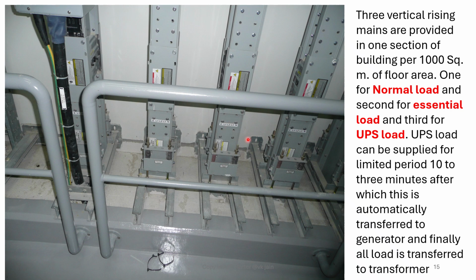Friends, the figure on left hand side shows the real life rising main systems, vertical rising mains, one, two, three. This real life vertical rising main system is provided for three different purposes. The first one may be normal, feeding the normal load only through the transformer. The second one may be feeding the essential load which comes through generators. And third one may be the load fed through UPS. So this rising main is connected to UPS and distributes the power to different items which are on UPS, mostly computer equipment, computerized digital items.